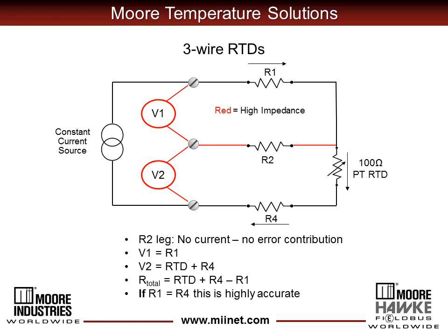When we're concerned about measuring accuracy, we have to realize that too many things work against making R1 and R4 identical. Wire gauge tolerance, work hardening of wires changes resistance. Even if no human error takes place in the installation, corrosion constantly works against us and perhaps is the major contribution to guaranteeing that R1 never equals R4.